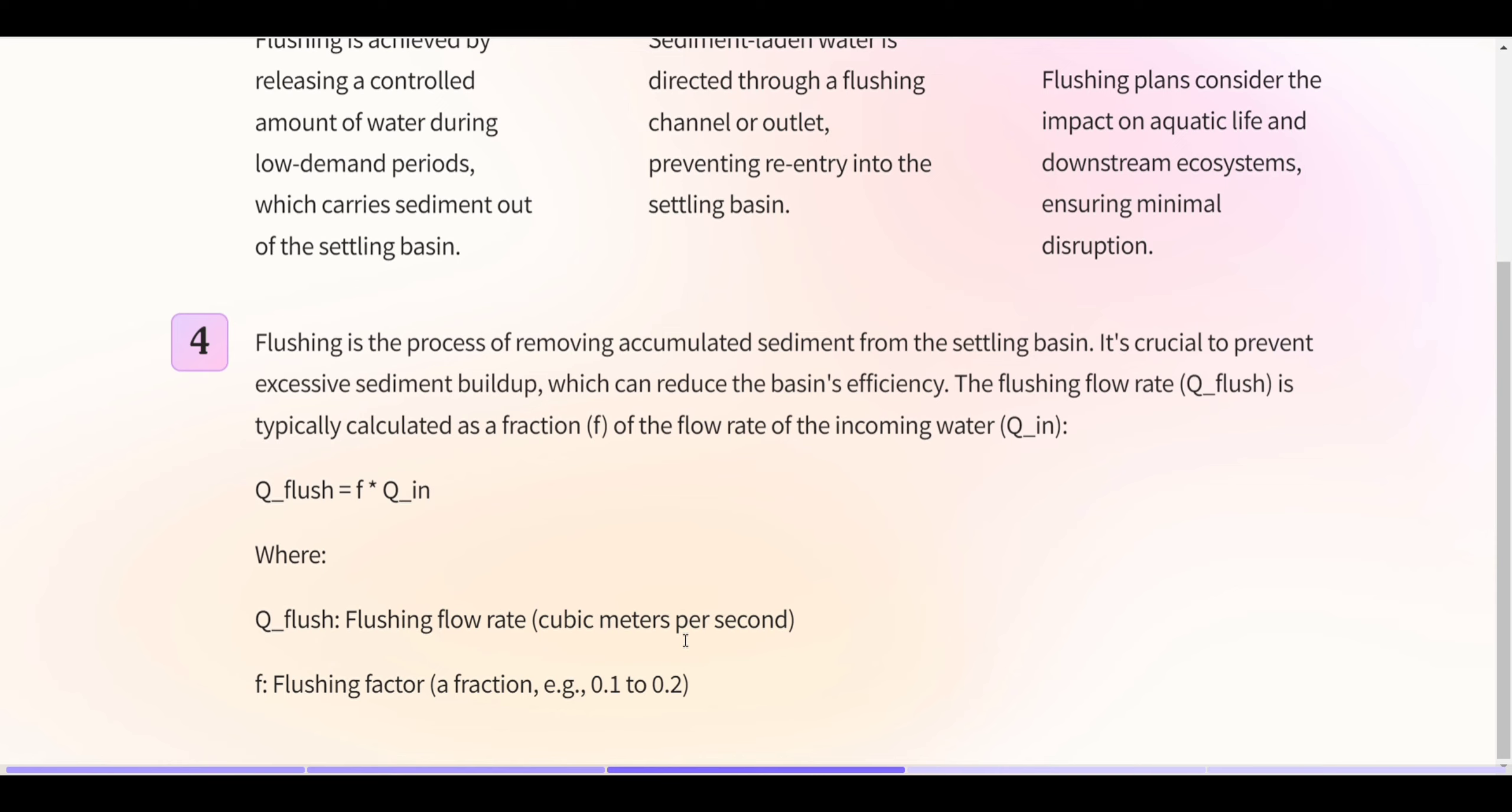Flushing is the process of removing accumulated sediment from the settling basin. It's crucial to prevent excessive sediment buildup, which can reduce the basin's efficiency. The flushing flow rate is typically calculated as a fraction of the flow rate of the incoming water: Q_flush equals F times Q_in, where Q_flush is the flushing flow rate and F is the flushing factor.